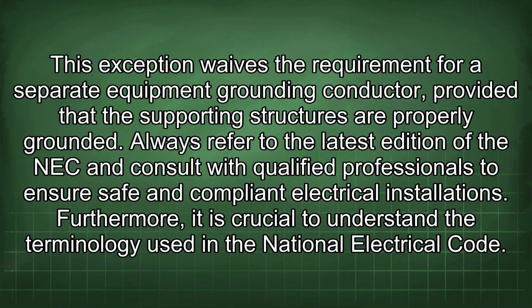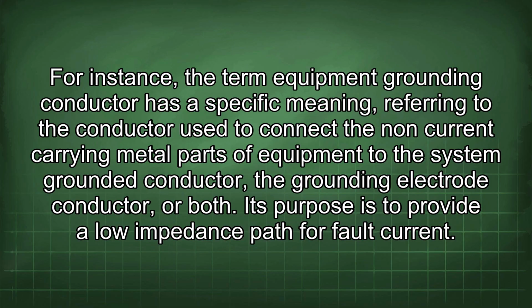Furthermore, it is crucial to understand the terminology used in the National Electrical Code. For instance, the term equipment grounding conductor has a specific meaning, referring to the conductor used to connect the non-current carrying metal parts of equipment to the system grounded conductor, the grounding electrode conductor, or both.